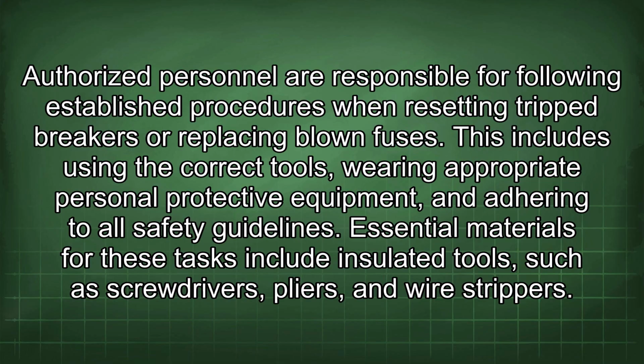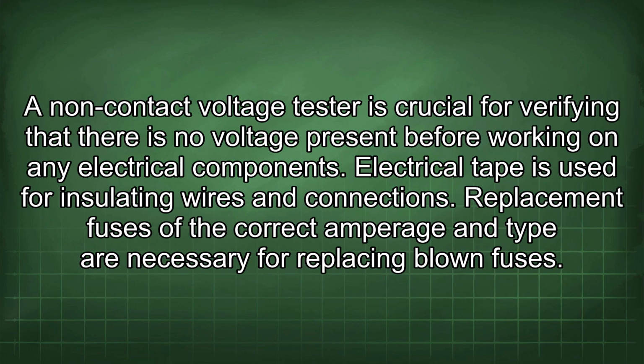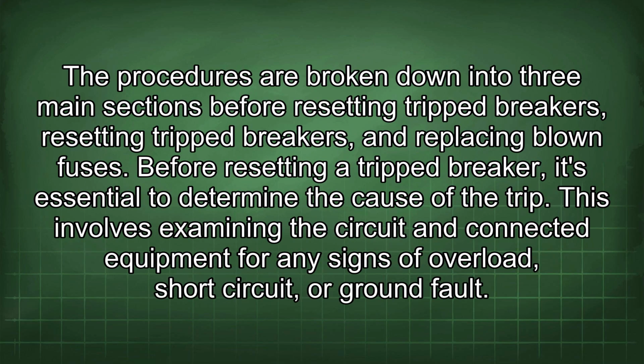Essential materials for these tasks include insulated tools such as screwdrivers, pliers, and wire strippers. A non-contact voltage tester is crucial for verifying that there is no voltage present before working on any electrical components. The electrical tape is used for insulating wires and connections. Replacement fuses of the correct amperage and type are necessary for replacing blown fuses. The procedures are broken down into three main sections: before resetting trip breakers, resetting trip breakers, and replacing blown fuses.